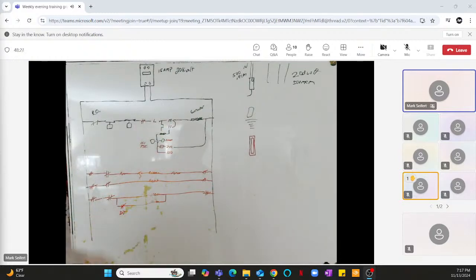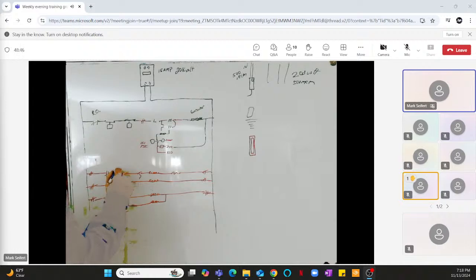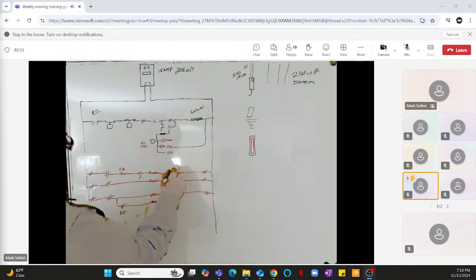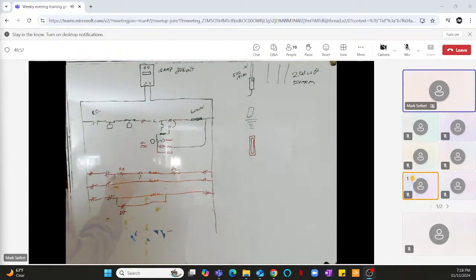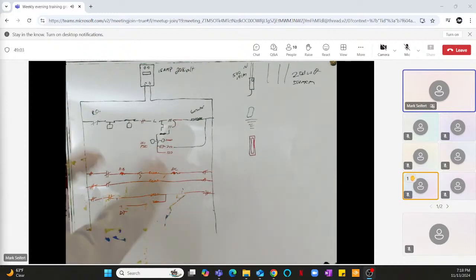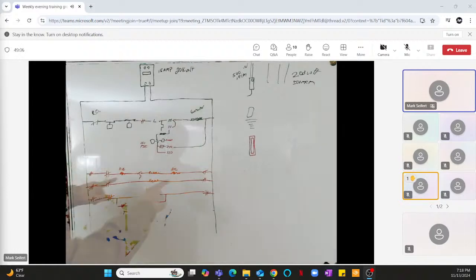Look on wiring diagrams. A lot of your wiring diagrams on the newer cases are going to show you which terminals are which, and they'll be labeled wherever it goes out to a case. Let's just say this is system A1. It'll say A1B or whatever, A1C, but it'll be labeled little terminals here where the electrician's going to come in and pull his wires in from the case and land them on these terminals up in the rack.